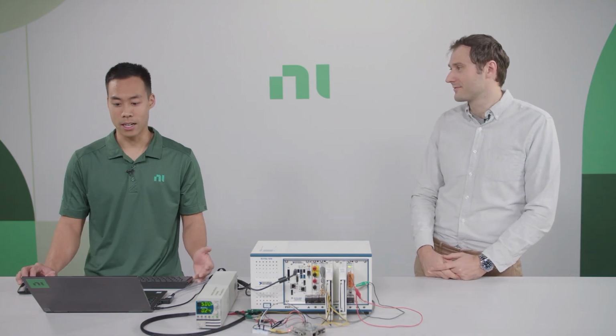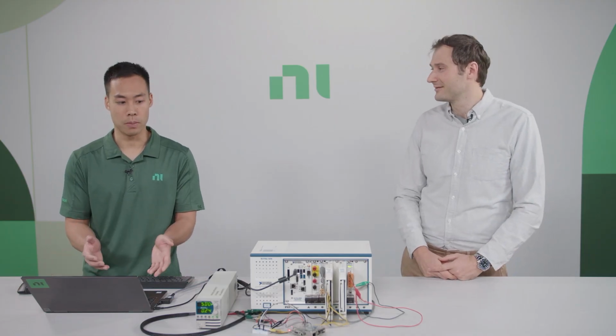So the last thing, I'm really happy about the benchtop measurement, but I want to move to automation. Can you help me with that? Oh yeah, that's the $1 million question, Daniel. So yeah, to go to automation takes less than a minute, and it's done through TestStand. So let's launch TestStand, which is a sequence software that NI provides.